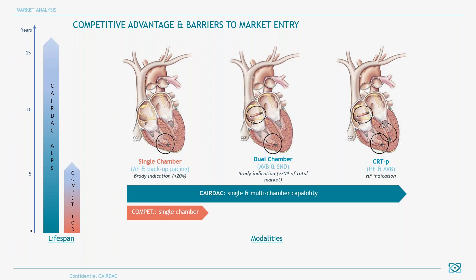On the other axis, the fact that our leadless capsule is powered by an energy harvester means that we will be able to add functions, even if they are power consuming, as long as this power is not higher than the power produced by the harvester. Even if a competitor today can introduce, for example, communication with the same size of capsule, they are going to reduce the longevity of the device. In our case, we can see the energy harvester as an upper limit of power consumption, but if the average power consumed by the device is lower than the energy produced by the harvester, we can add extra functions. So the concept of the product is a self-sufficient pacemaker.